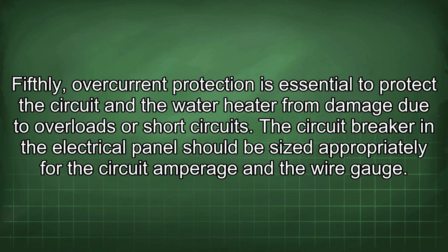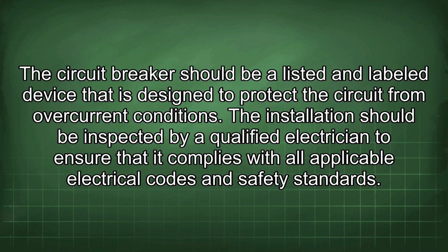panel. Fifthly, overcurrent protection is essential to protect the circuit and the water heater from damage due to overloads or short circuits. The circuit breaker in the electrical panel should be sized appropriately for the circuit amperage and the wire gauge.